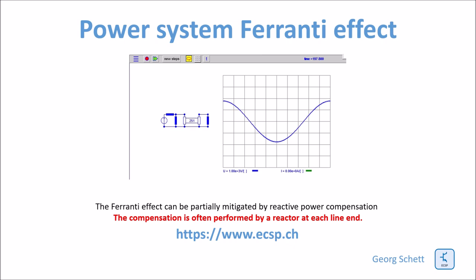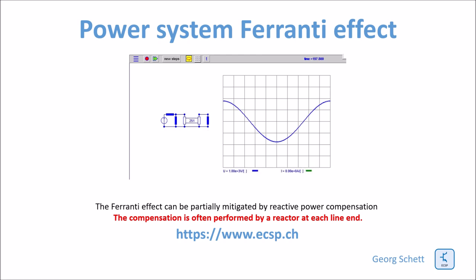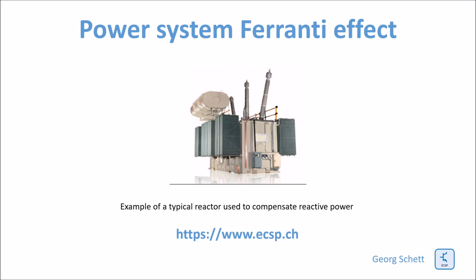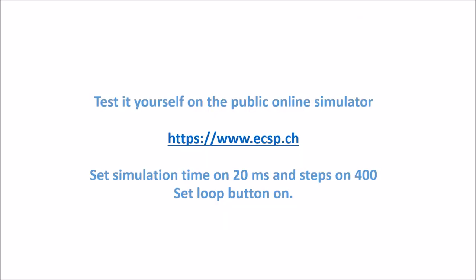To reduce the Ferranti effect and overvoltages at the line end, I would install a reactor at the line end, switched on either always or just under low load conditions. Normally I would also place reactors at both the beginning and end of the line, subdividing the reactive power compensation rather than concentrating it at one end. In the simulation you can now see what happens when varying the reactors at both line ends. Here you can see an example of such a high voltage reactor placed at one or both line ends. You can go to the simulator and experiment with it yourself, as it is a straightforward simulation.